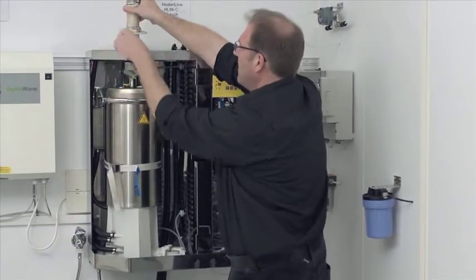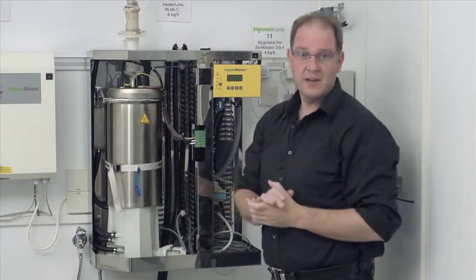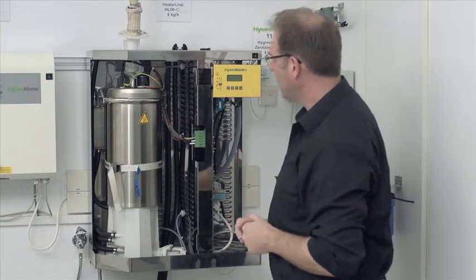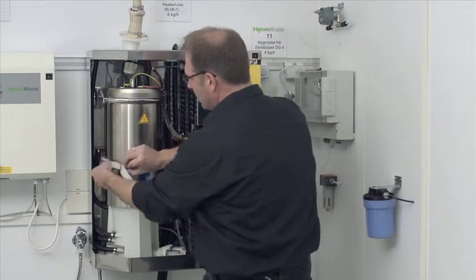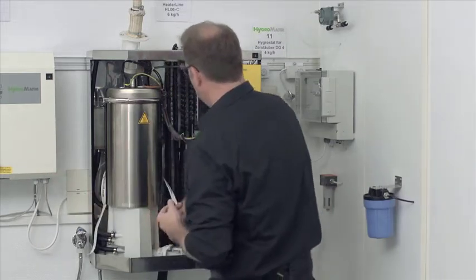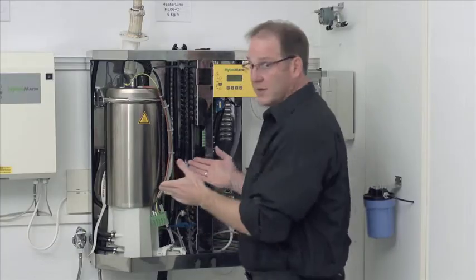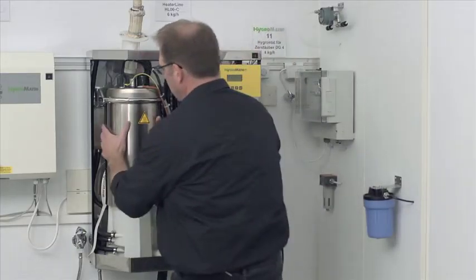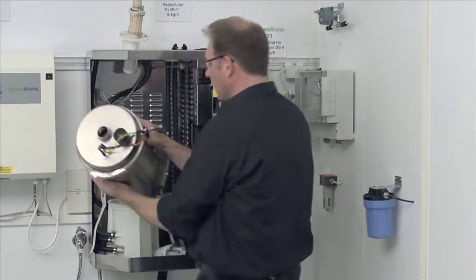I now take the clip again, attach it up here, and then have my hands free so I'm able to handle the cylinder. Next step is to unfasten the cylinder clamping belt, pull off the system connector. Then I can disassemble the cylinder with a light twisting motion. I can then take it out.